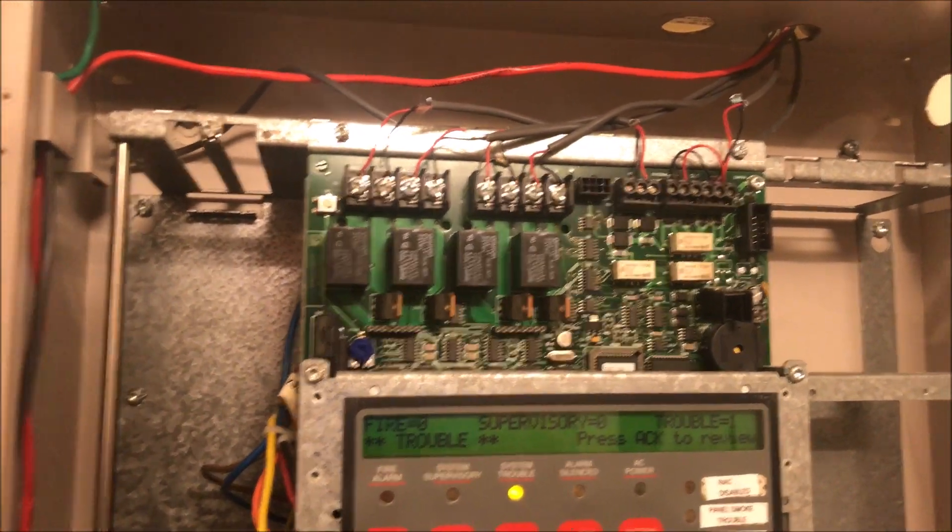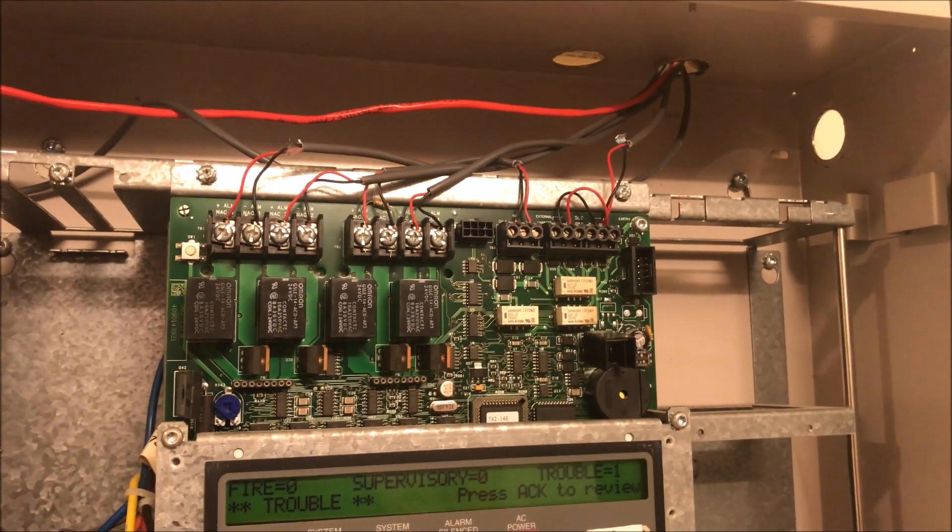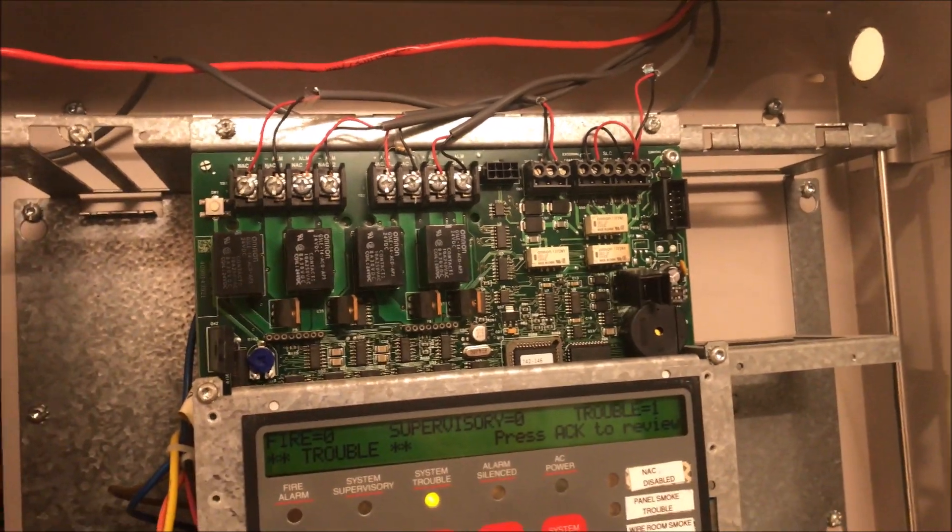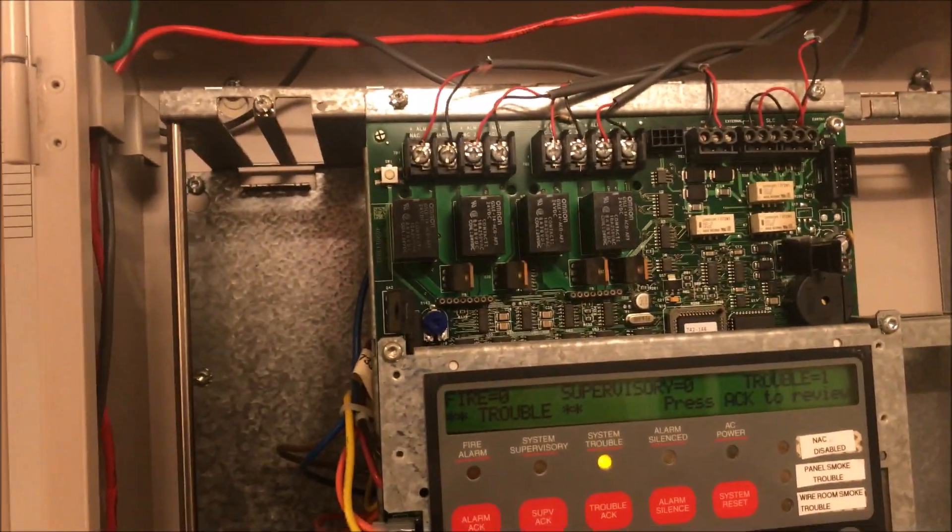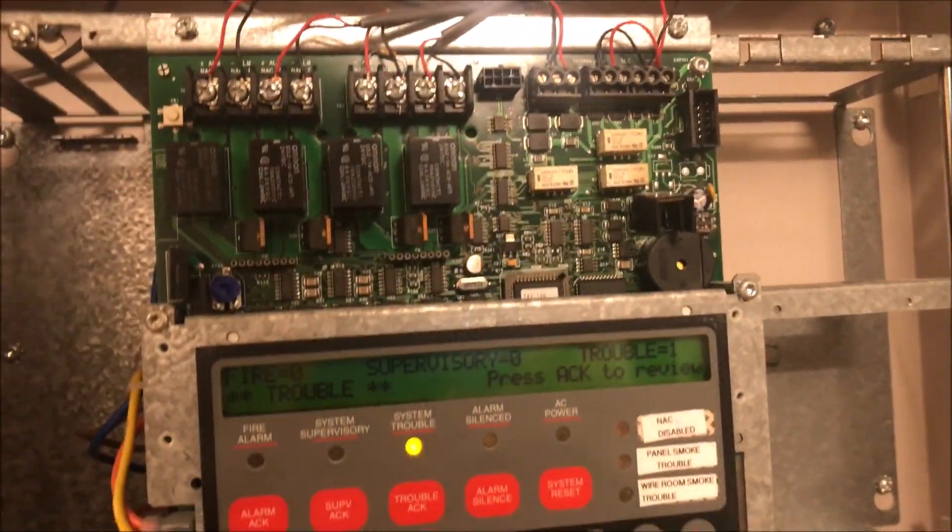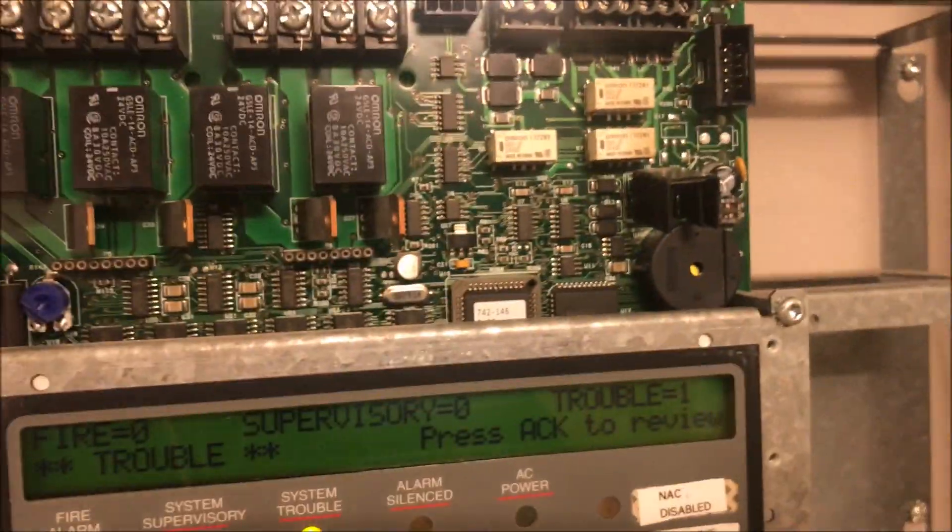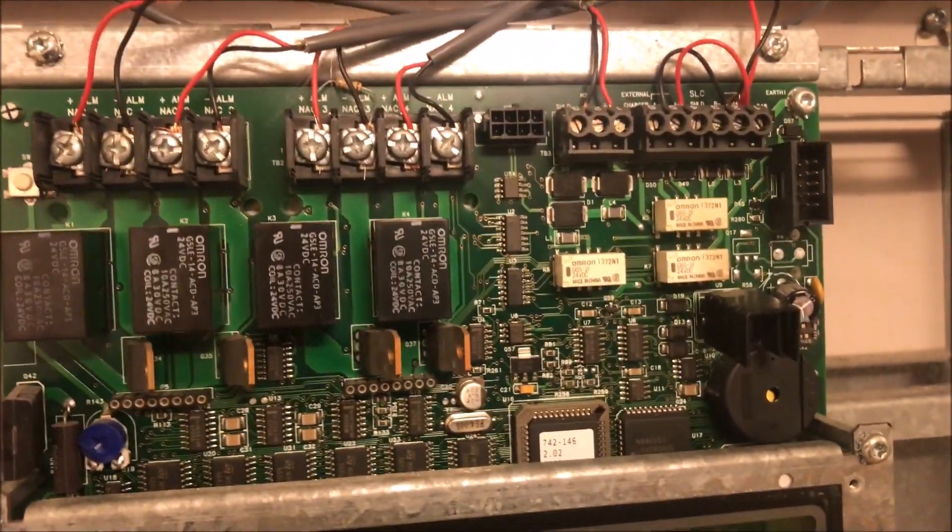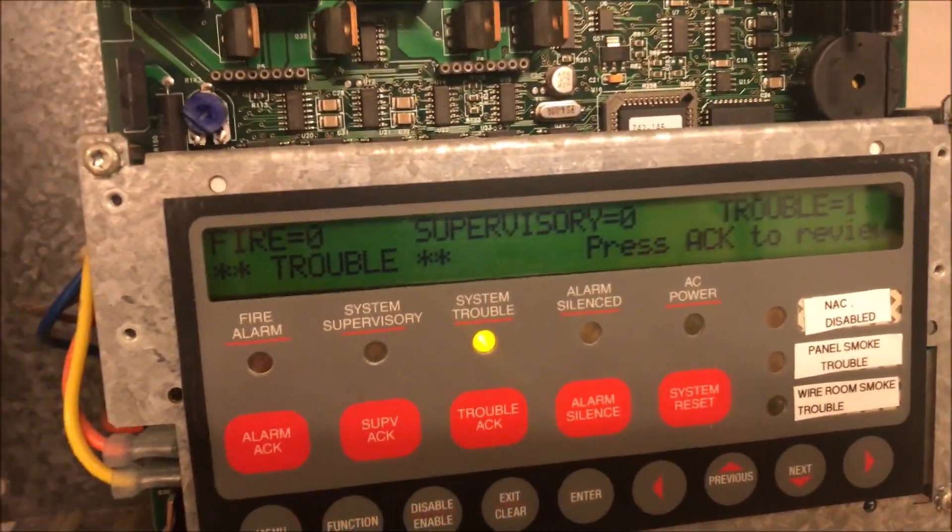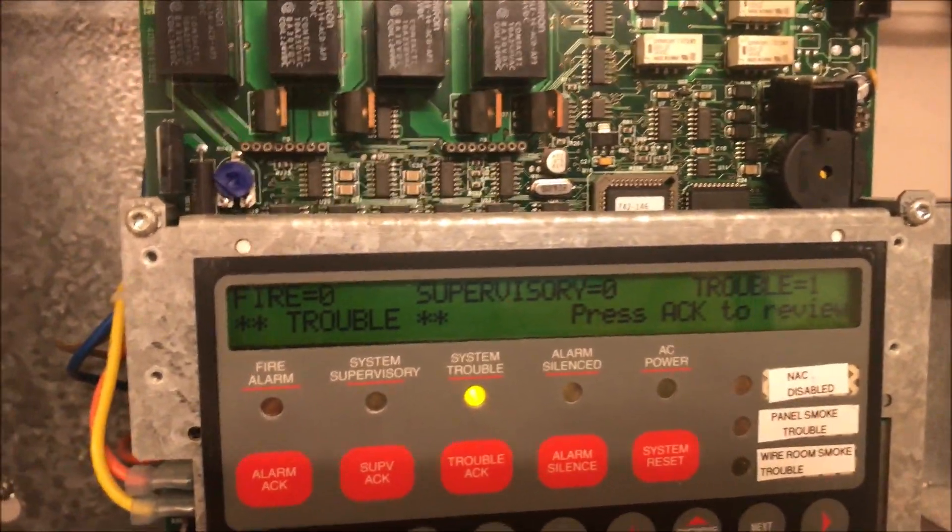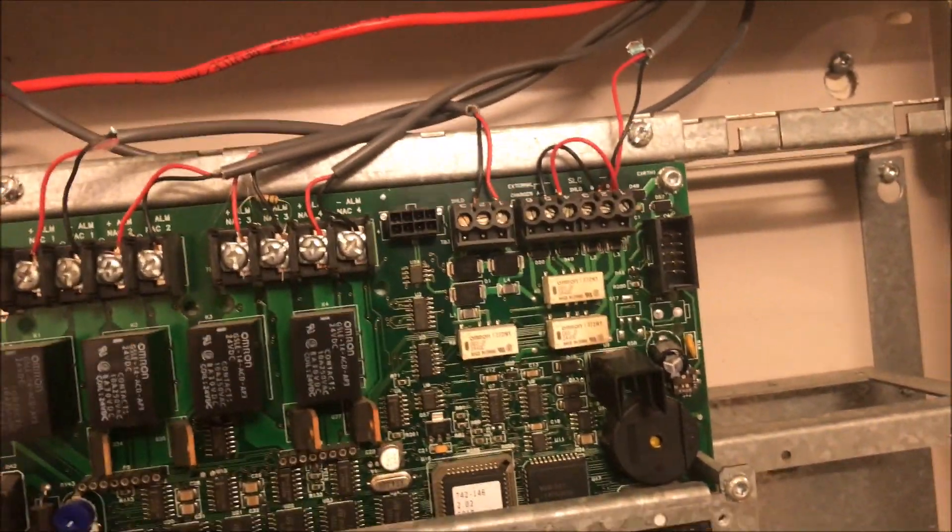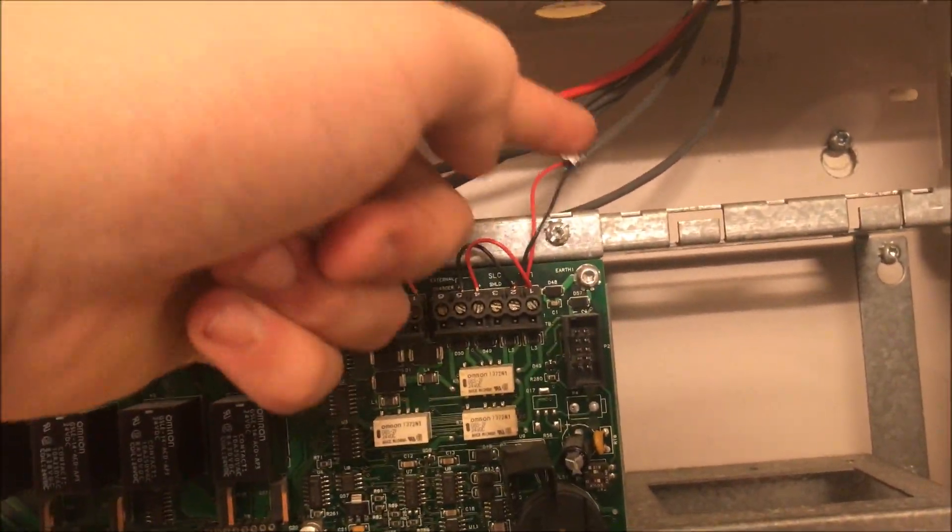I think we covered everything. Because it's an addressable panel, it's actually pretty simple to wire up. You don't have to worry about all the zones and supervision for each zone because it's self-supervised. It's listening for the pings from each point, so you don't have to worry about end-of-line resistors with your initiation points. If your point goes down, it'll say either 'weak' or 'no answer' on the screen and give you a trouble.